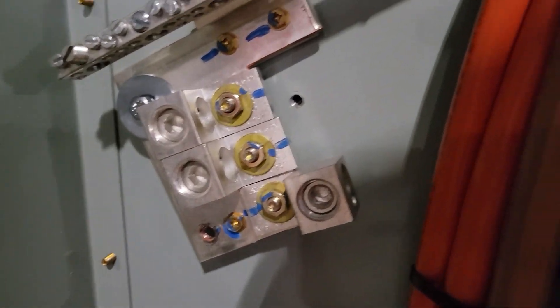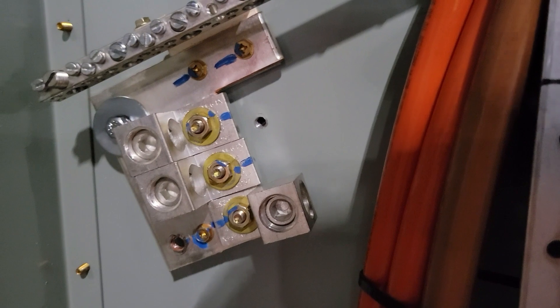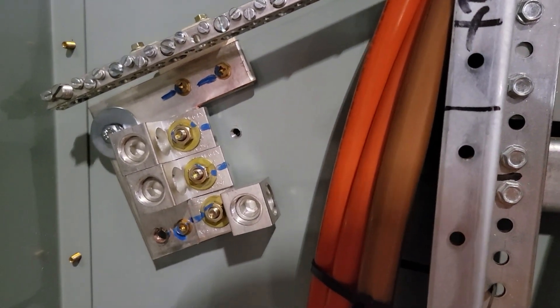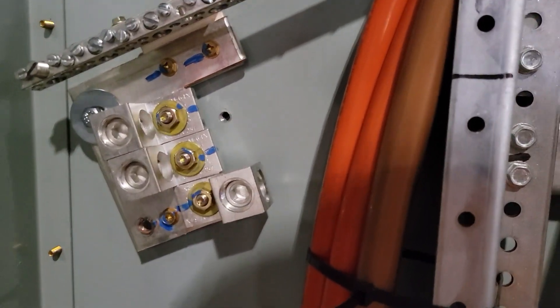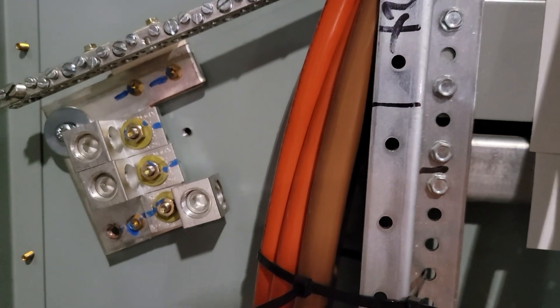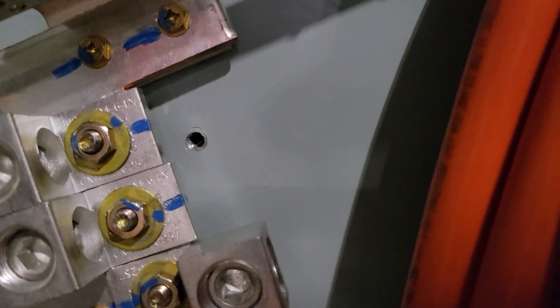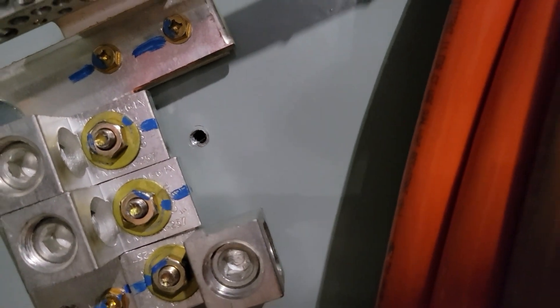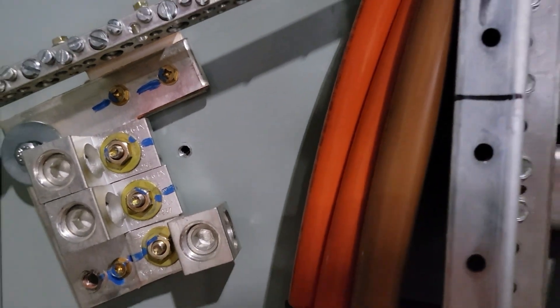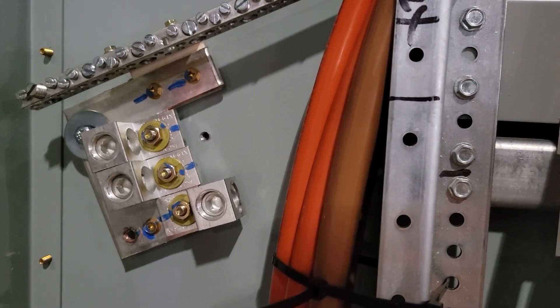let you know that anytime you're installing an equipment ground, a building ground, a grounding kit—anything you install that bonds something to your grounding system—you cannot use a sheet-metal screw.